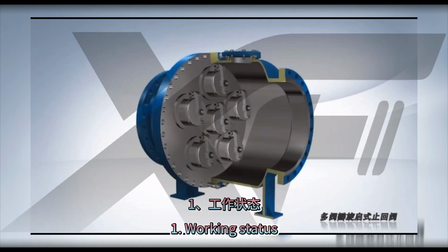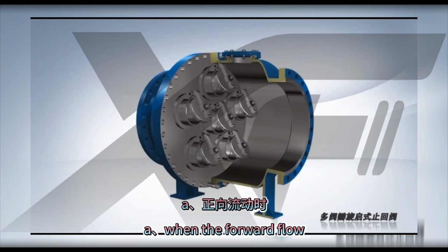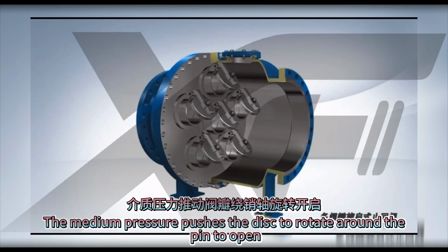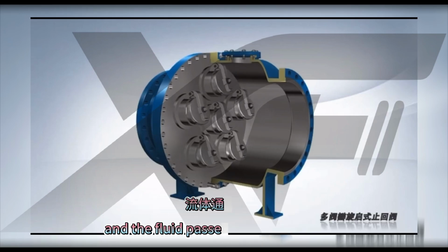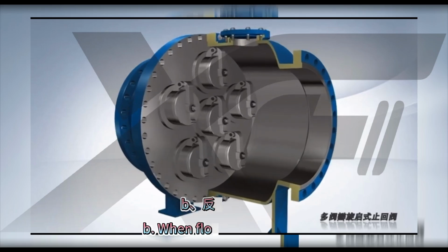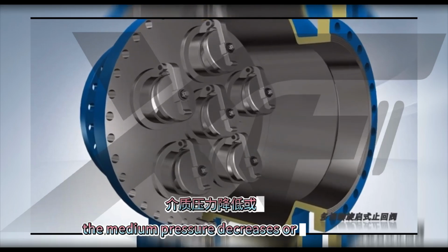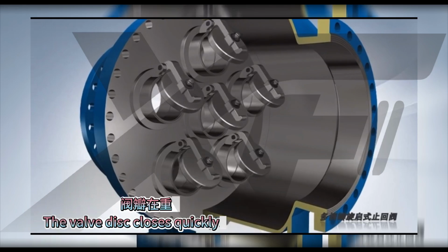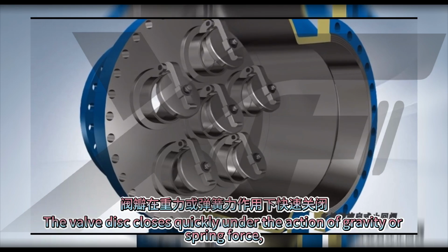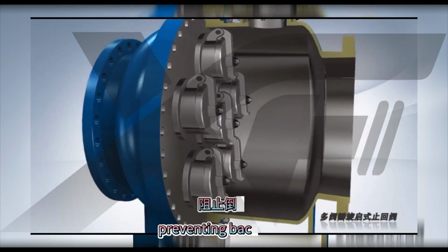1. Working status. A. When flowing forward, the medium pressure pushes the disc to rotate around the pin to open, and the fluid passes through the valve. B. When flowing in reverse, the medium pressure decreases or backflows. The valve disc closes quickly under the action of gravity or spring force, preventing backflow.